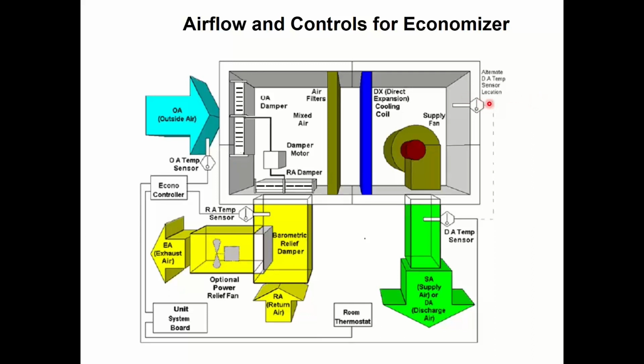I'm going to put a sensor in the system. Typically it gets mounted over here in the fan section. It could be mounted in the supply duct, but that's rare. It's typically mounted in the fan section. On large systems, so bigger than a packaged rooftop unit, we typically get a sensing element, a mixed air temperature sensor that goes down in the middle over here. But on small systems, it ends up being a small, tiny sensor that gets mounted in the fan cabinet.